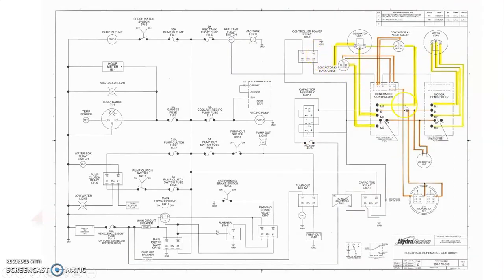And then the AC circuit, you can see diagrammed here. From the generator, you have the 3 legs, the 3 AC phases. 2 of the phases, phase 1 and phase 3, are interrupted by these solenoids. Those solenoids are controlled by the generator controller.